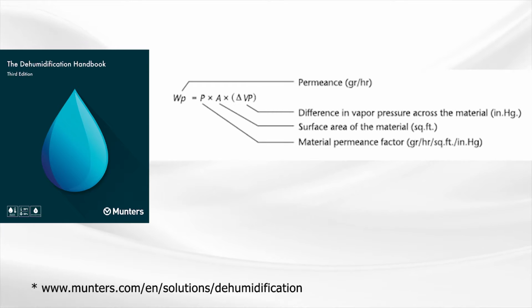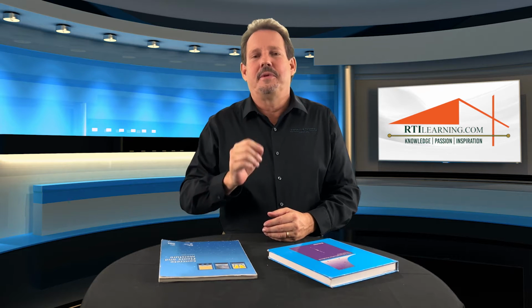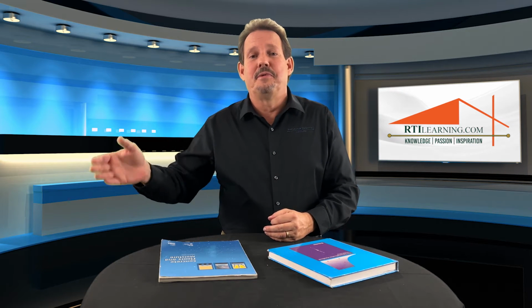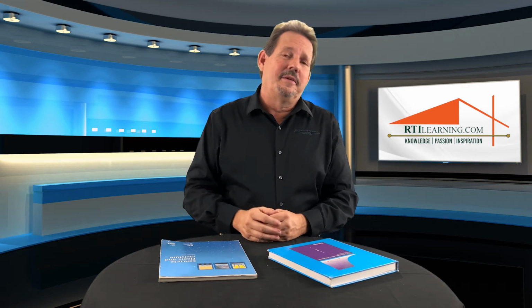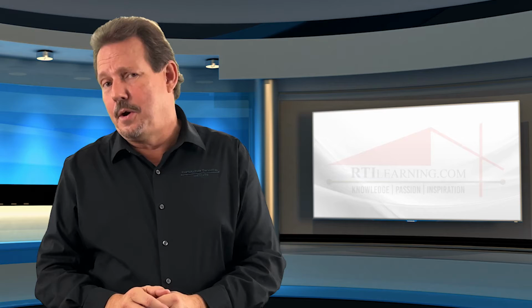So once you get the permeance factor of your material, you multiply that by the surface area and then the vapor pressure differential between sides A and B of the material. And that will get you your permeance of that material, or how fast the water is going to move through that material.